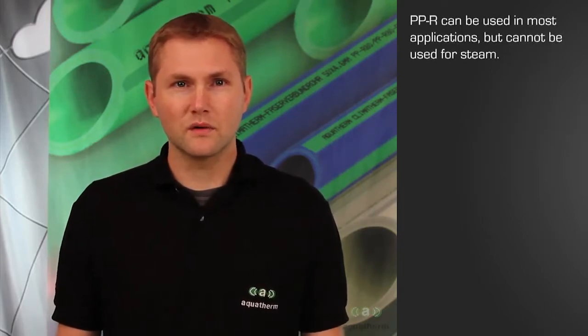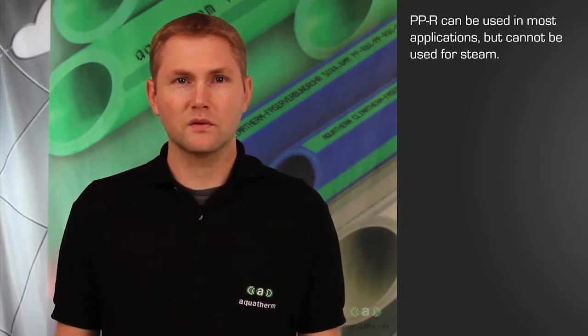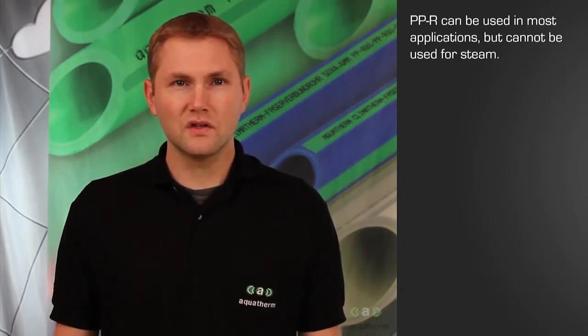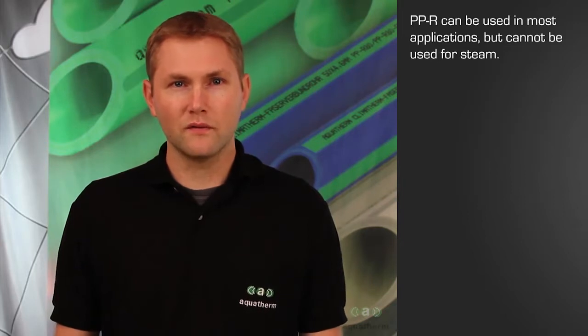There are only two noteworthy disadvantages of using PPR. The first is that PPR cannot be used in steam applications. If the material is altered to withstand the heat of steam, it becomes difficult to install. Fortunately, many engineers are moving away from steam in favor of more efficient systems, so this is less and less of a concern.